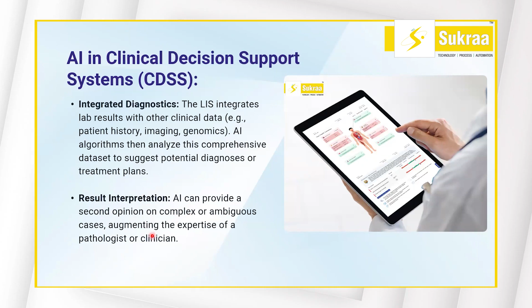Result interpretation should be available as a second opinion on complex or ambiguous cases, especially for histopathology, cytology, and microbiology. Most important when you are doing laboratory auto verification are the delta checks. The delta checks refer to automated result validation tools which compare the current test report to the previous report on a historical basis. And if there is a difference between these two beyond a predefined limit, as set by the global standards and the CLSI guidelines, the LIS automatically flags that the current report may not be released, and it requires a review by the technologist, scientific officer, pathologist, or microbiologist.